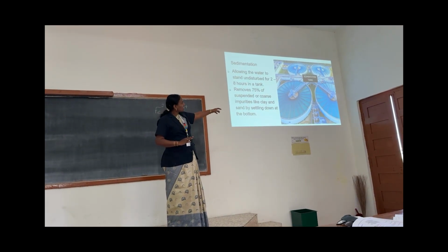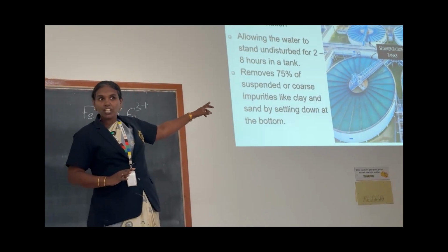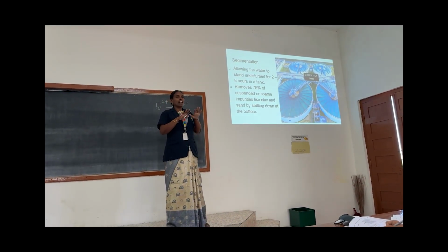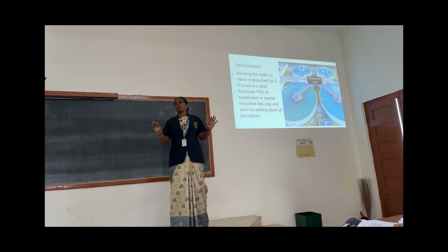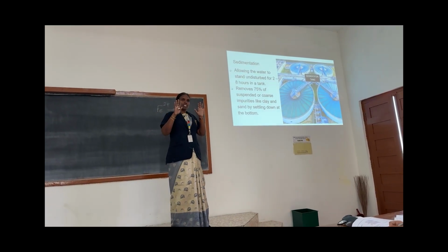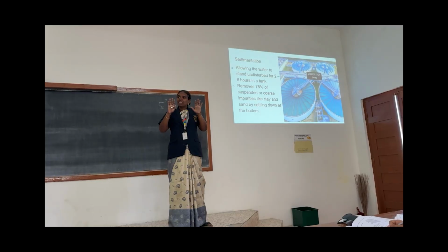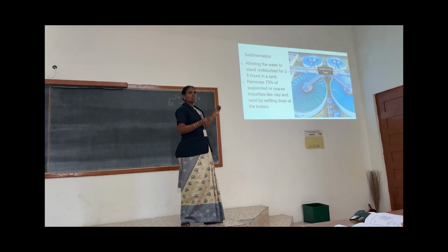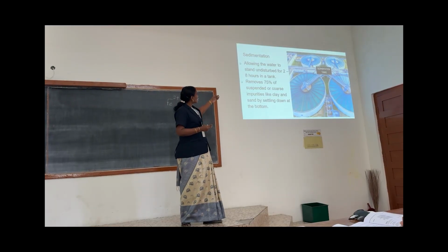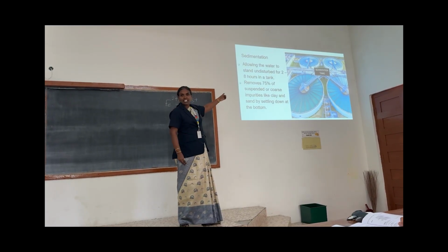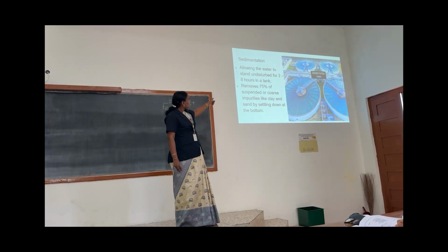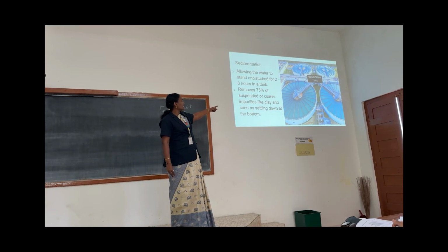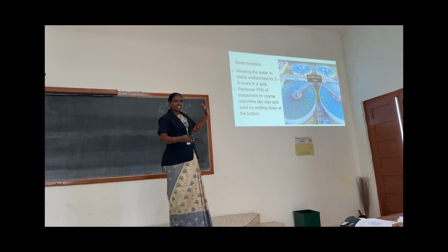Yes, next. Sedimentation. See, these are all sedimentation tanks. Could you able to see? What we have to do? We should not disturb the water. We are allowing the water to settle, so any suspended particles present will settle down in 2 to 8 hours. It removes 75% of suspended or coarse impurities like clay and sand by settling at the bottom.